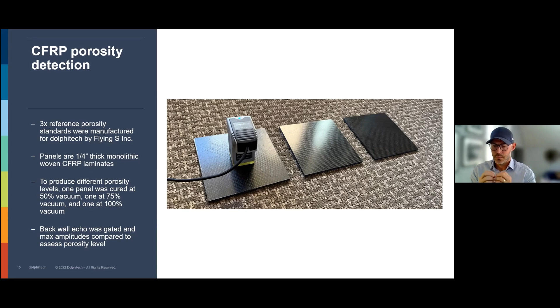And here I'm showing how we set this up. You can set it up with some requirements. For example, on the back wall, you calibrate with a perfectly healthy 100% vacuum sample and say we will approve everything that is between 40% and 100% back wall reflection. Everything under that we set as pink, so it is very easy to detect. That's what we've done here. You can see the 75% vacuum has a lot more pink, which is bad and not approved. And the 50% vacuum has even more pink, which is even worse.